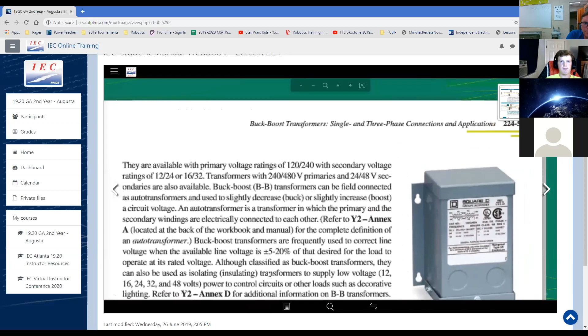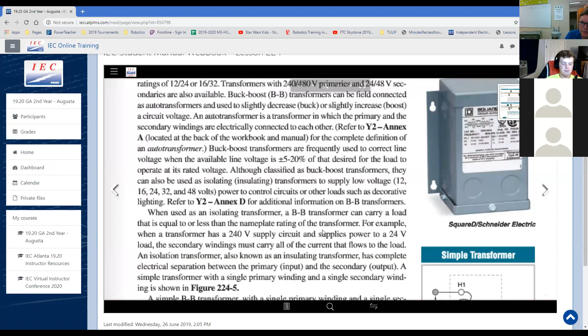The complete definition of an auto transformer is in the back of the workbook, and by the way, if you got a chance to look through, make sure you got Annex D out. We'll get to that. When used as an isolating transformer, the buck boost can carry a load that is equal to or less than the nameplate rating of the transformer.